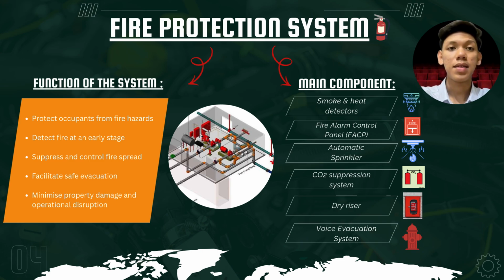The fire protection system is designed to protect the lives of building occupants and minimize property damage during a fire emergency. The first objective is to detect fire as early as possible so that immediate action can be taken before the fire spreads. The second objective is to control or suppress the fire using systems such as the automatic sprinkler and CO2 suppression system. Another objective is to ensure a safe and orderly evacuation by activating the fire alarm and voice evacuation system to guide occupants to the nearest emergency exit. Overall, this system helps create a safe environment for students, lecturers, and visitors throughout the building.